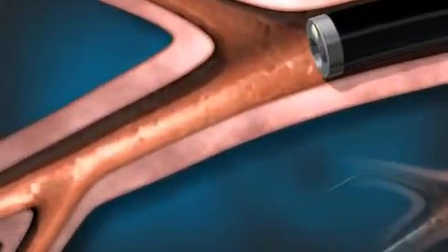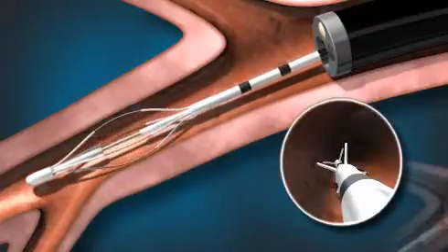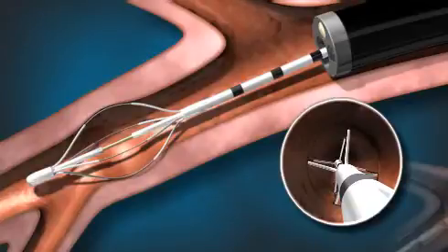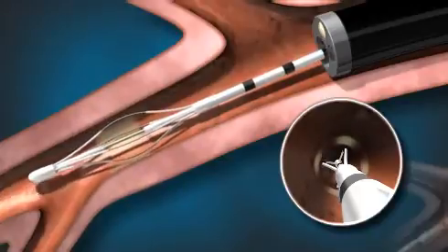The Alair device has an expandable wire-electrode array at the tip, and when it is expanded, the arms of the electrode array come in contact with and fit snugly against the airway wall. The expanded electrode array then delivers controlled radiofrequency energy for about 10 seconds to heat the airway smooth muscle.